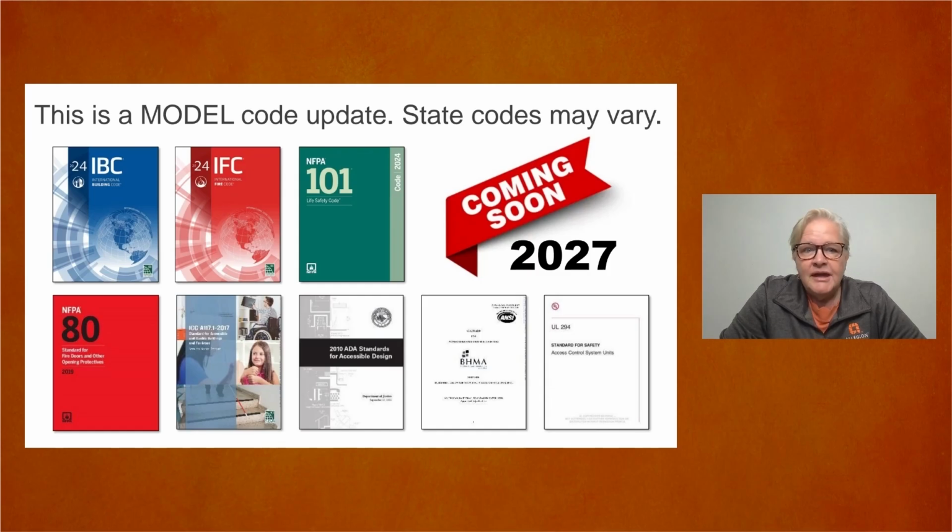For example, if you work in a healthcare facility, you might be saying, we still use the 2012 edition of NFPA 101, which is the case for most healthcare facilities. In that edition, only 2 sections of the special locking arrangements require the UL 294 listing for hardware.